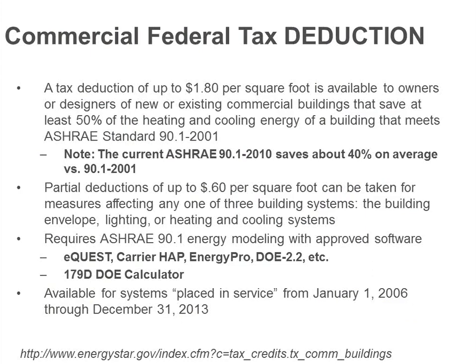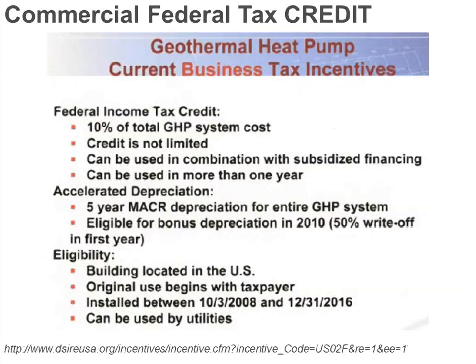The whole entire building. So basically, this involves energy modeling, and you get 60 cents per square foot for the building envelope, 60 cents for HVAC, and 60 cents for lighting, for a total of $1.80 per square foot to improve the efficiency on the whole building. So really, it applies to rehab projects, not really a replacement of a single piece of equipment. And this does expire at the end of this year. If you want more info on it, I've got the website down on the bottom there, or you can just Google 179D tax incentive or something like that, and you should get the details pop up for it.